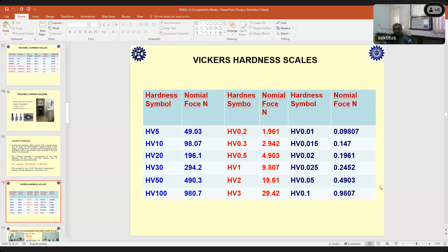So this is the hardness standard machine, the HV machines we have here in NPL. It has a scale of HV1, HV2, all these scales. Naturally in the higher scales, if you are applying a larger force, then the indentation diagonal will be very large, so you can make a good measurement. The uncertainty in HV50 and above is 1%, and in the lower scale, because of the uncertainty in the dimension measurements and the angle, it is very high. The best uncertainty you can get in the micro scale is 1.5%.